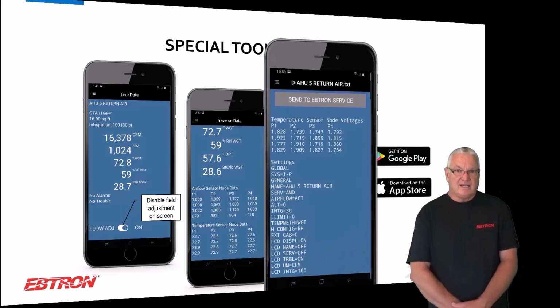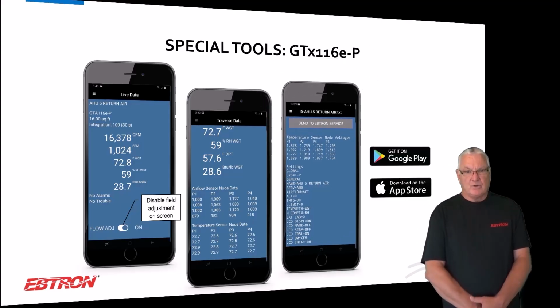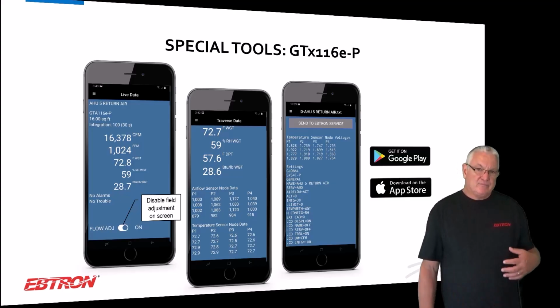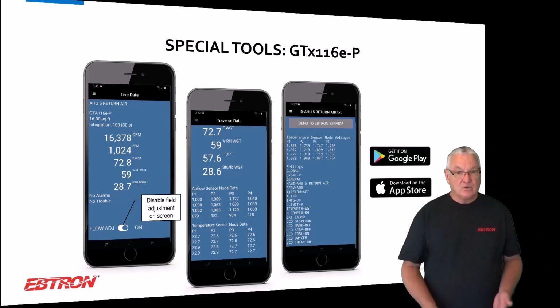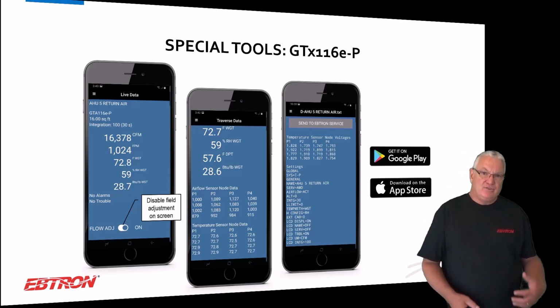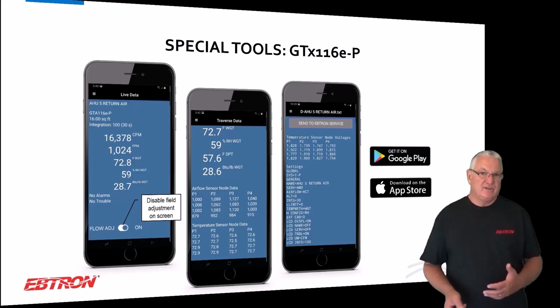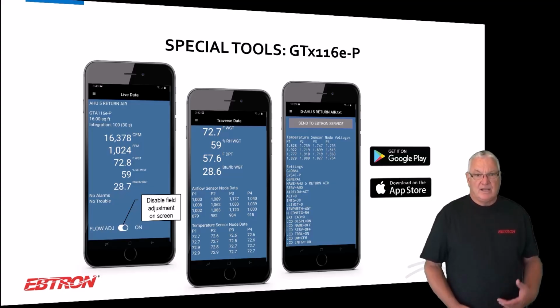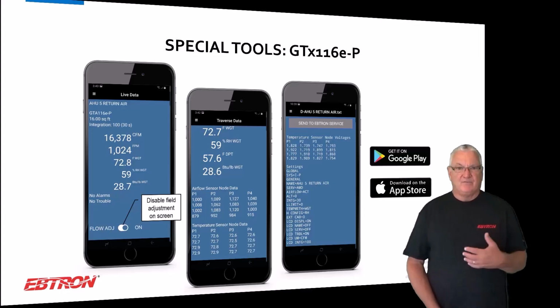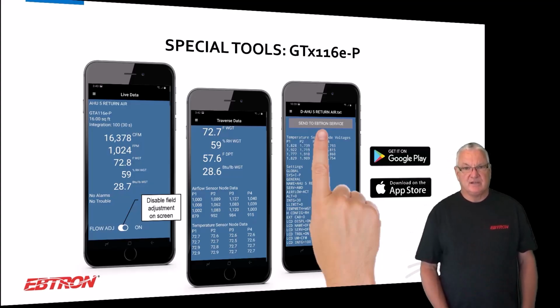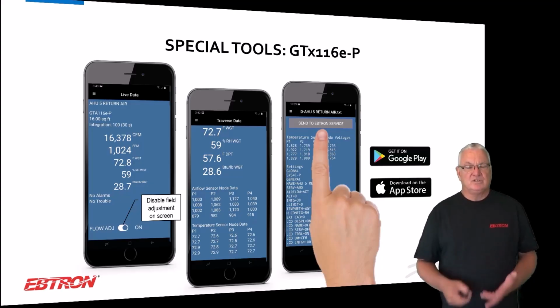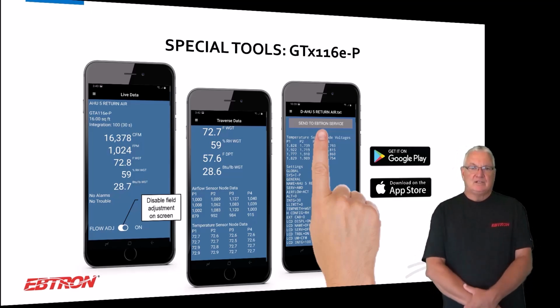And finally, there's a diagnostic screen that'll show you what all the parameters are set to, as well as any active trouble codes, any historical trouble codes. And what you do there is if you have a problem, first of all, I think it's a good thing for you to go out and just shoot this and save it if you made any changes to the device. But the other good thing about it is, you have some questions, something isn't working right, you don't want to get on the phone with customer service and go back and forth. You simply click the Send to EBTRON Service button. It'll go to the service department so that when you call the service department, it's all there for them to look at.